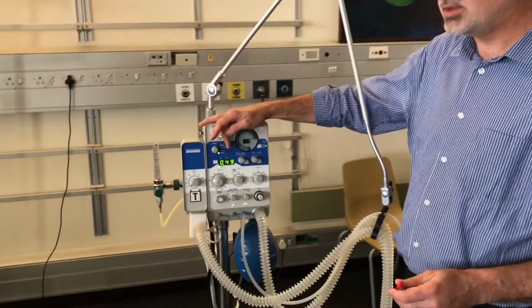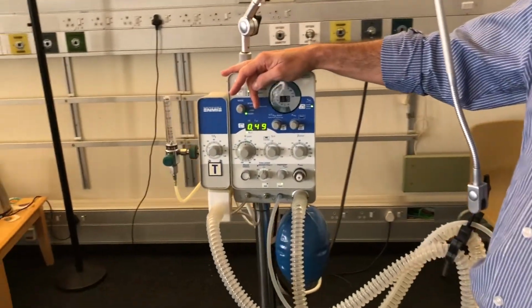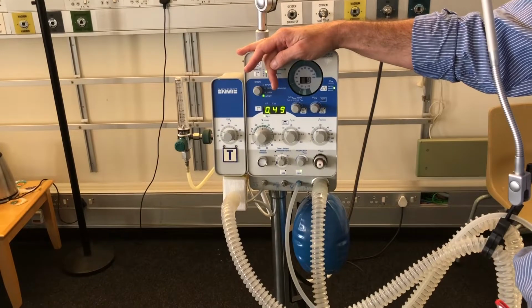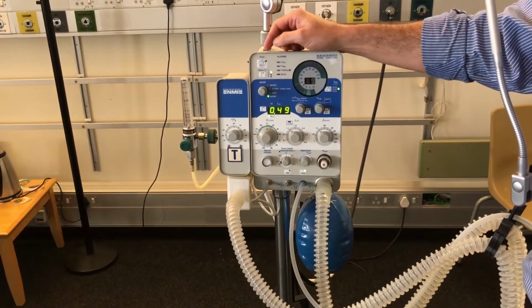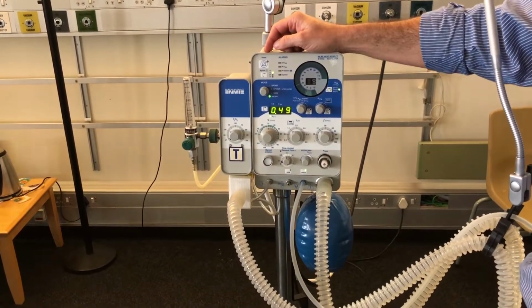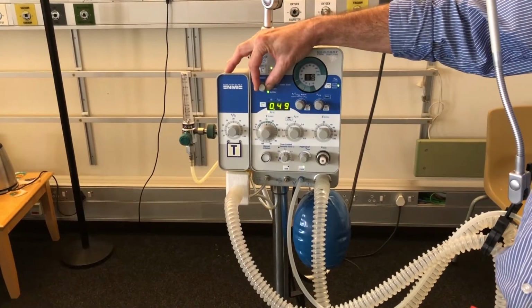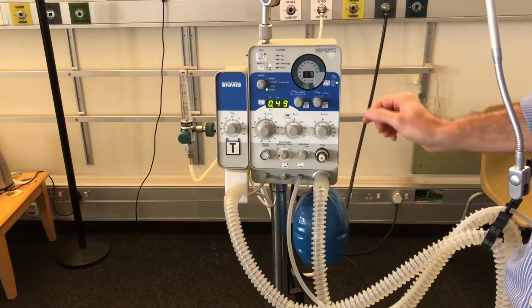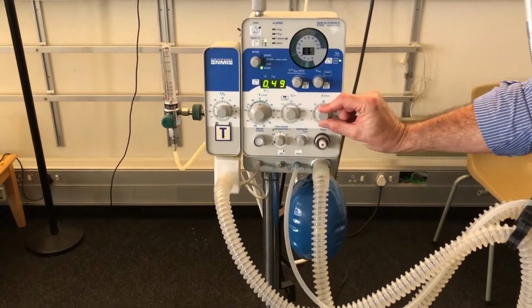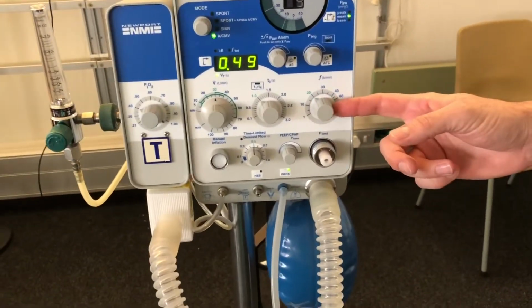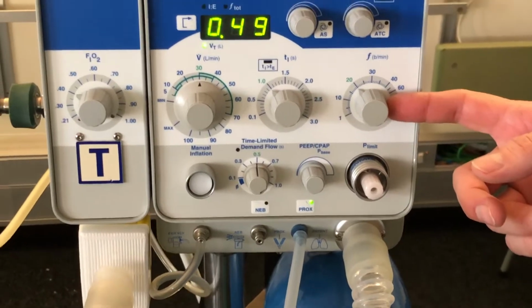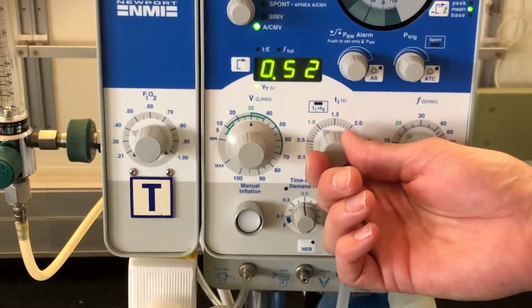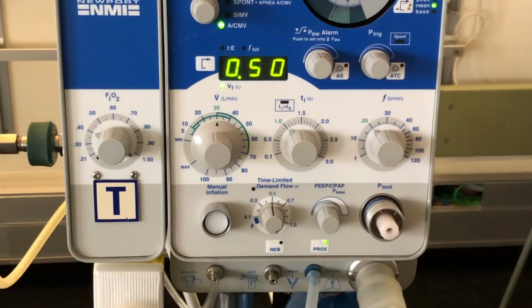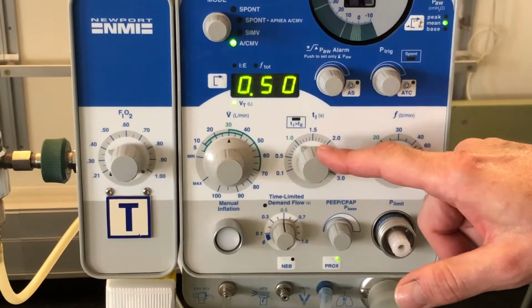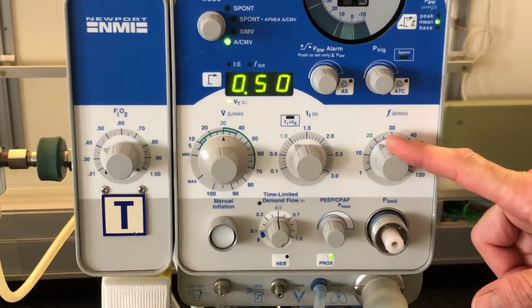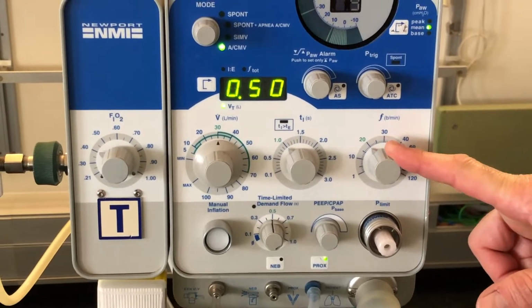So assist control, then the machine will either assist or control the breath, depending on whether or not the patient makes any effort. So I'm just going to go through the settings on assist control as we have it at the moment. So the patient's set up to get 20 breaths a minute, so that's one breath cycle every 3 seconds. And the inspiratory time I've set there to be 1 second. So clearly if there's 1 second of inspiration in a 3-second respiratory cycle, then the IE ratio should be 1 to 2.